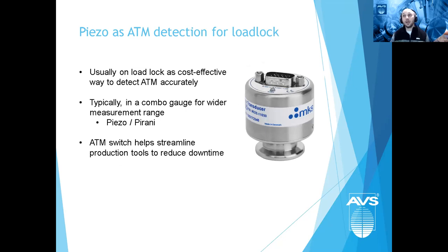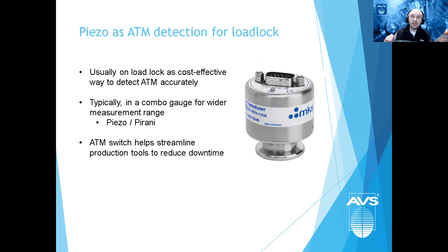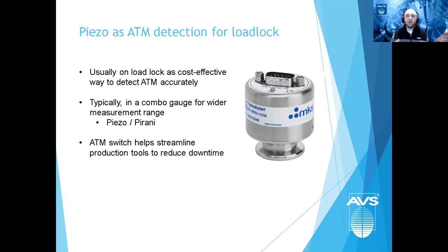A piezo gauge is also useful for load-lock atmospheric detection. On a load lock, where you're transferring a sample into a process chamber, the piezo's low cost and fast response automate the process — confirming true atmospheric pressure — to streamline production in high-throughput tools and reduce downtime.